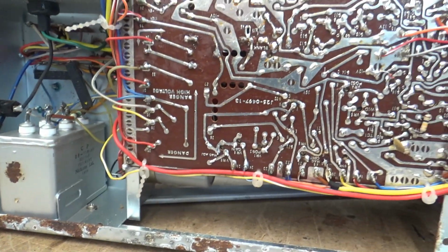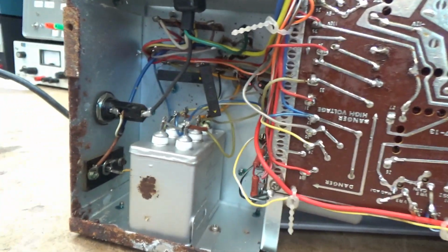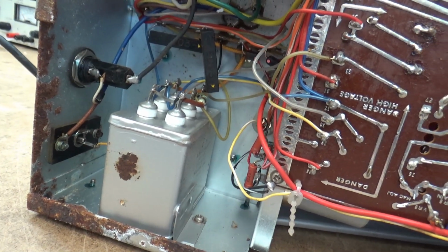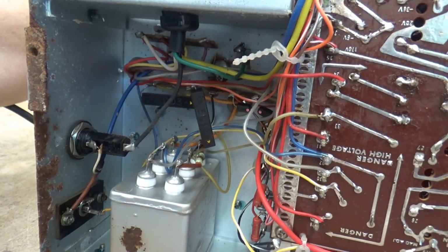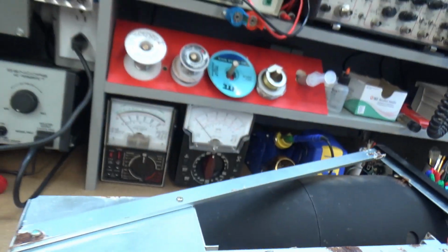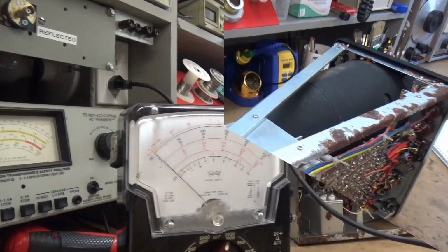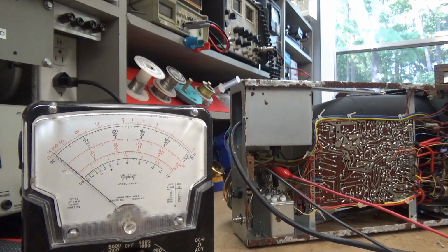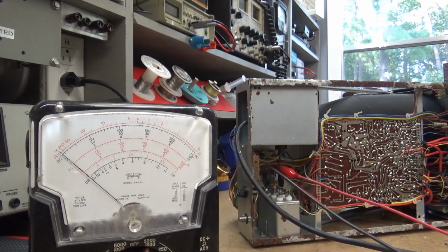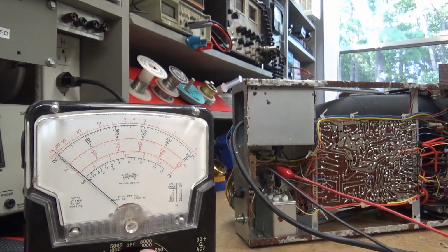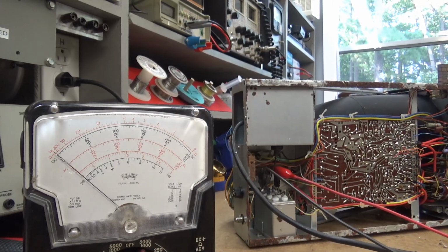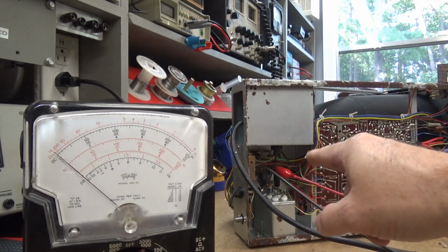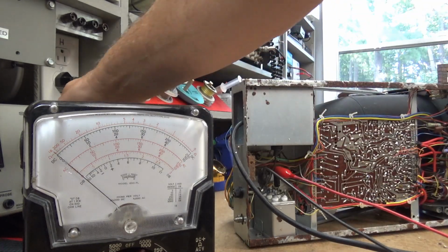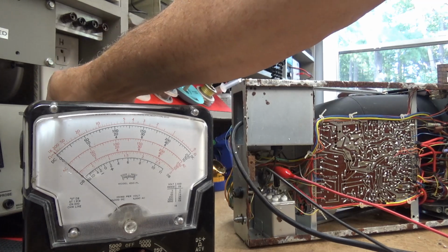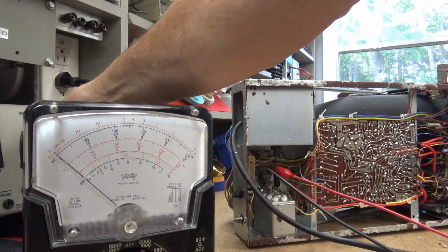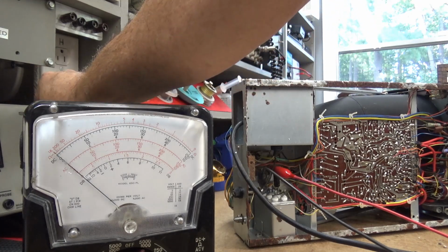So how do we want to proceed? We'll turn this voltage all the way down. We'll hook up the Triplett to it. So let me get that done and we'll be right back. Alright, so I got my Triplett 630 right here. Connected, set it for 1000 volts AC. And I've got it on the high voltage secondary coming out of the transformer. So I have my variable AC power supply turned down to minimum. So we're going to fire it up.